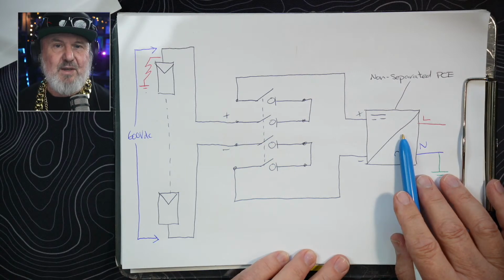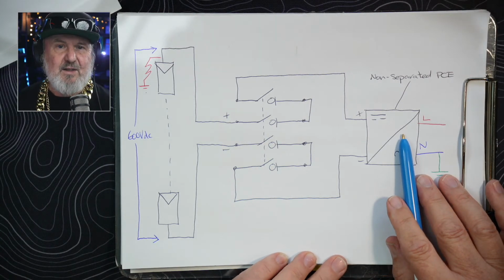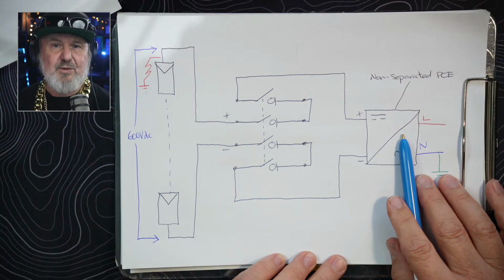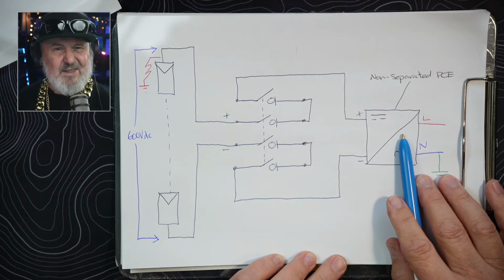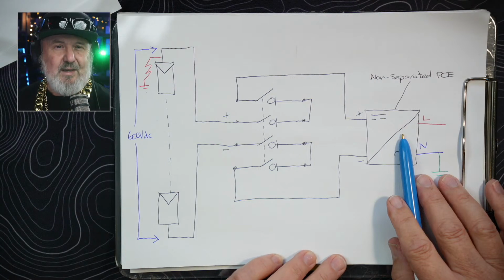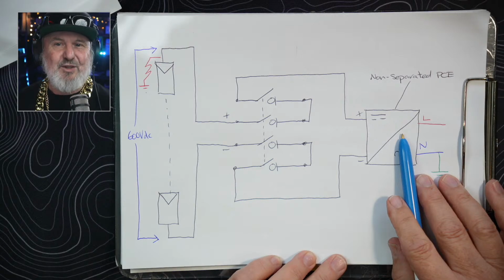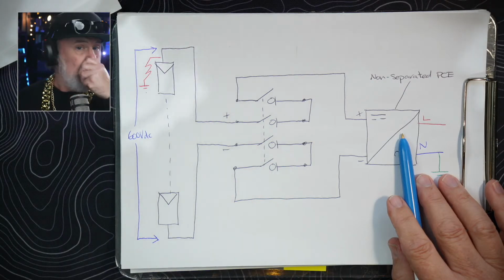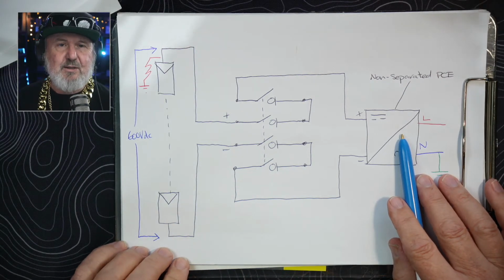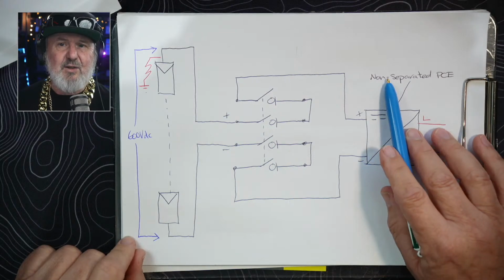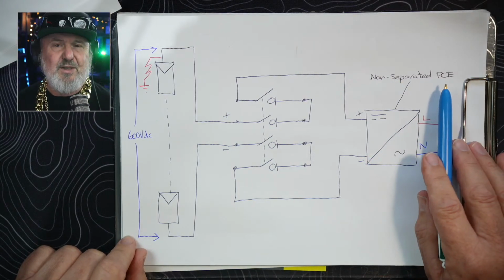So in a way, it means the inverter can identify that there is an earth leakage to frame or other and shut down. But if that's what's known as a bolted fault, i.e. a really low impedance connection, so the wires have been chewed through and are resting firmly onto the frame or rail, we've got a really good bolted earth. We now have an unfortunate situation with a non-separated inverter, or PCE.